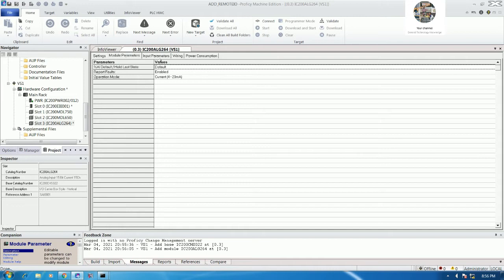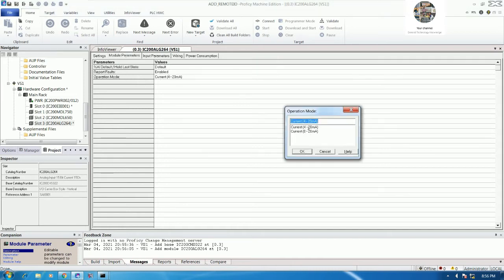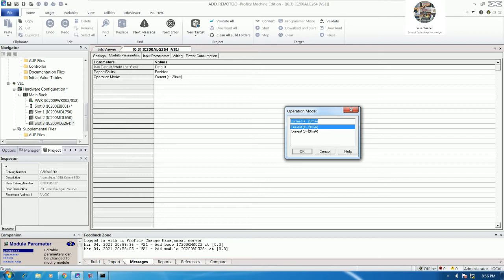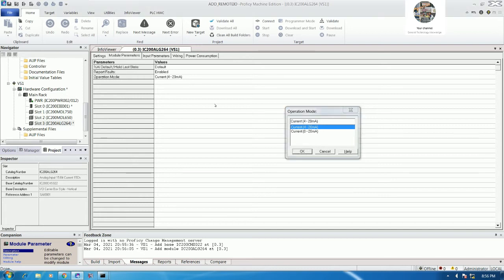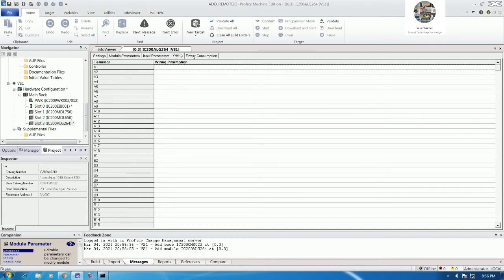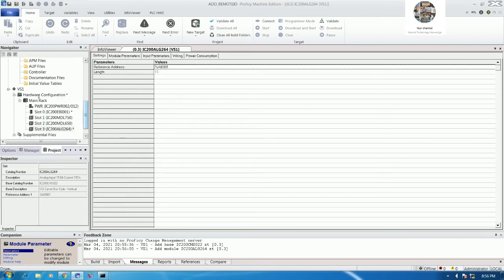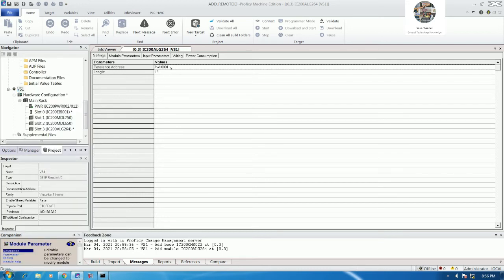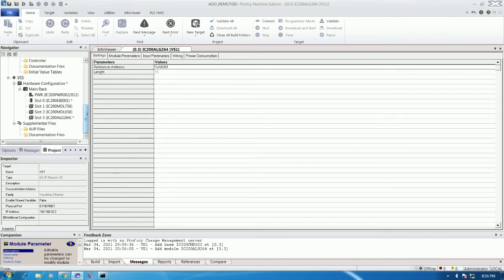There are two options: the first is 4 to 20 milliamp, the second is 0 to 20 milliamp. Since I have a standard source of 4 to 20 milliamp, I will select that option. No other settings need to be changed. The address will start from %AI1. If we check the I/O table, it starts from %AI1.